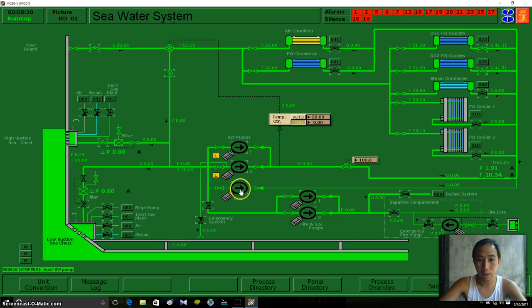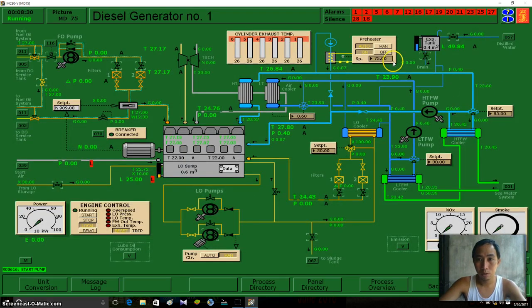We'll be starting our auxiliary pump. Again, we're going back to our diesel generator number 1. So our cooling system, our preheater is switched on. Next, we'll be charging lube oil to our lube oil sump tank because it is low level. So we have low level here, we have low pressure here. So this is our starting air, this is our storage tank, and this is going to sump tank. We're going to fill it by simply opening the valve.